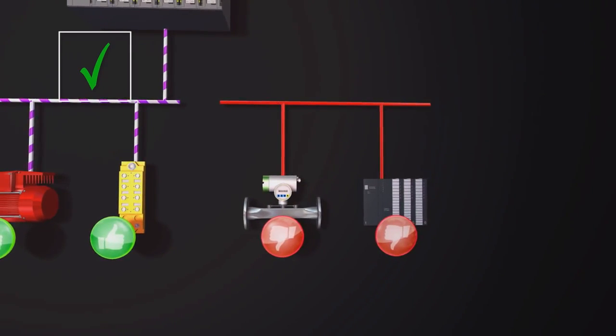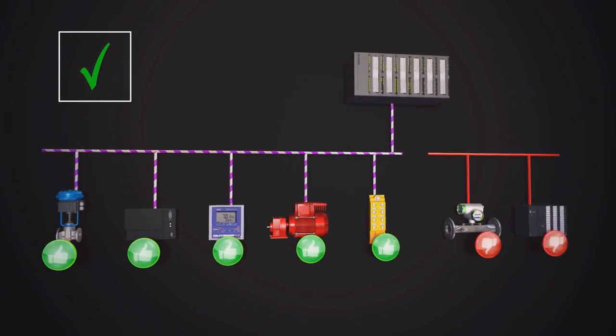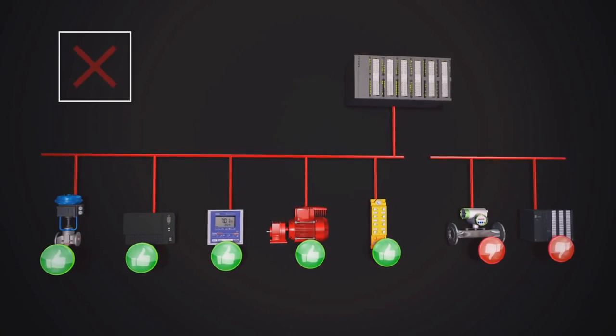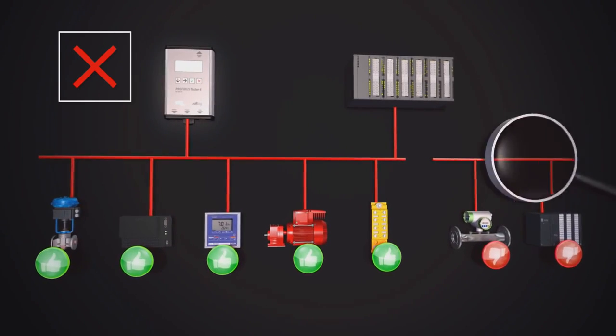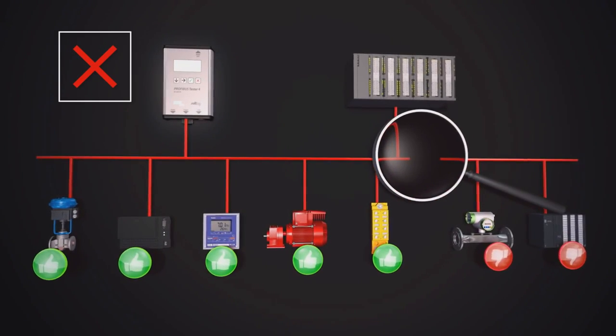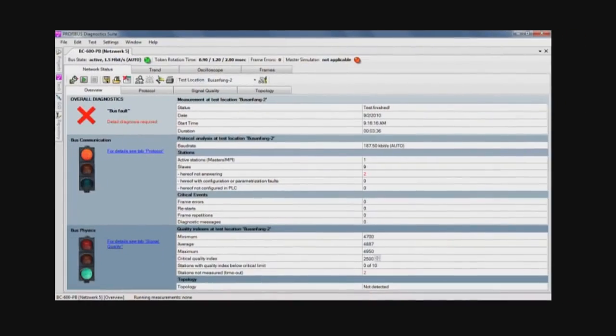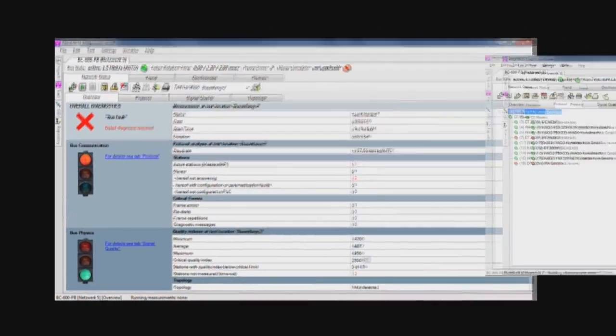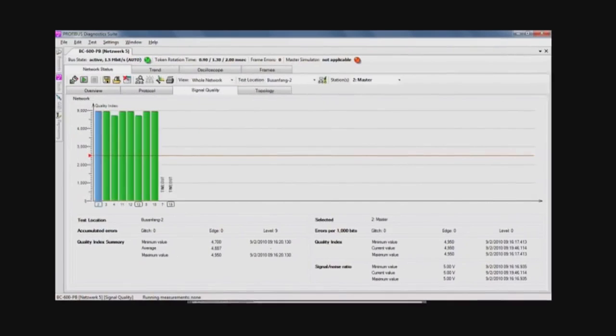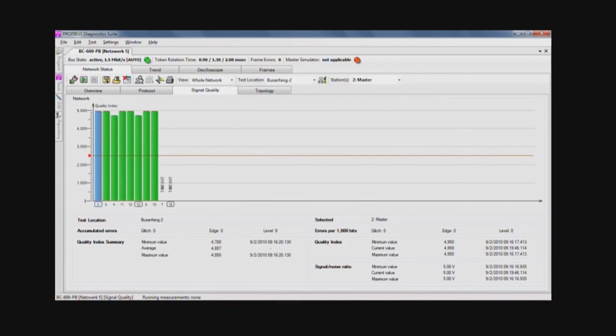The Profibus Tester 4 helps you to quickly and accurately identify and locate all types of bus problems. A special trend test is used for finding rare or sporadic faults over a prolonged period of time and covers both bus communication and bus physics.